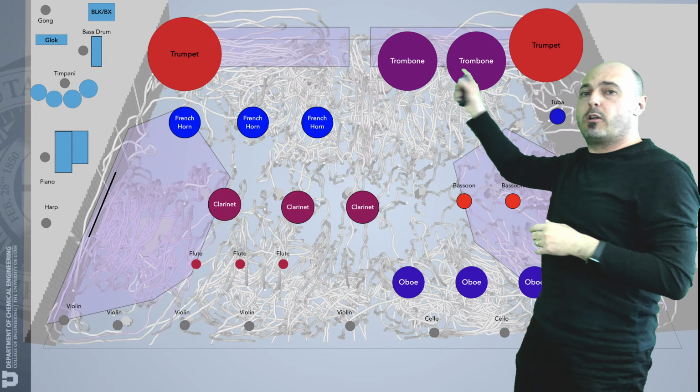Tony, one of them is, what were the velocities above the head of the players, the typical flow velocity above the head of the music player? About somewhere between 0.4 to 0.5 meter per second. So it's quite significant, right? Because HVAC norms tend to be, the comfort level is around 15 centimeters per second, right? 0.15. It still felt comfortable though. I mean, it was breezy, but it still felt comfortable.